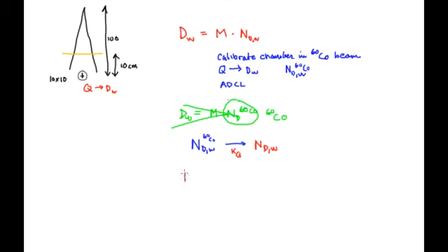It's just a number. So if you did that, then the dose to water would be your meter reading times this KQ times your NDW in the cobalt 60 beam. And then you would have your dose to water in the LINAC beam. So let's look at this KQ factor a little closer.